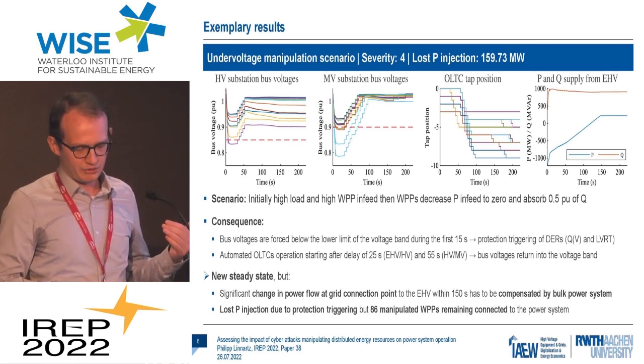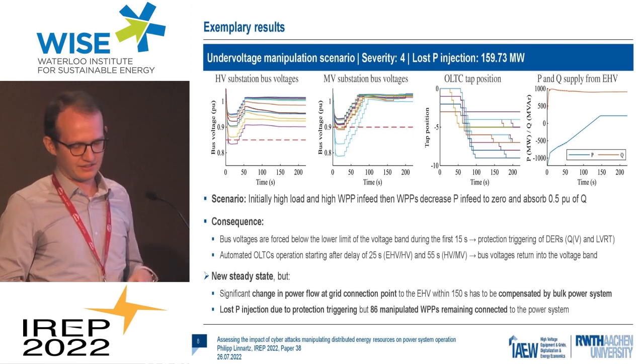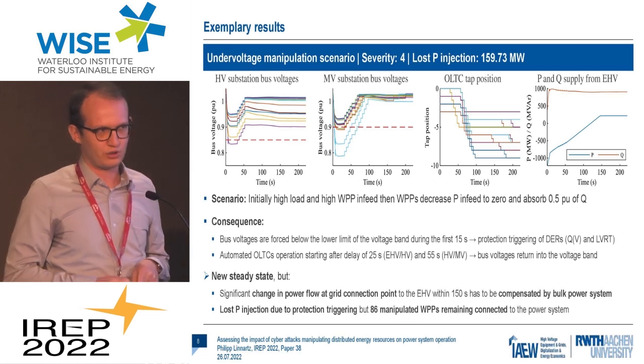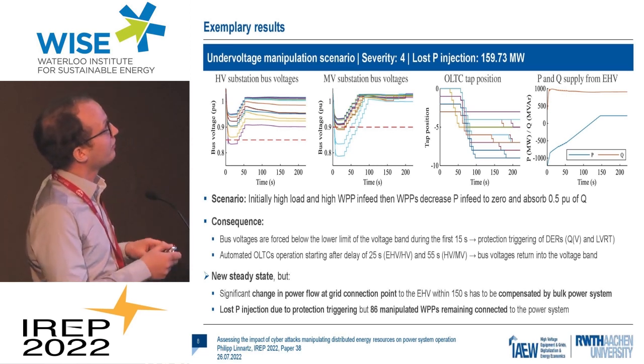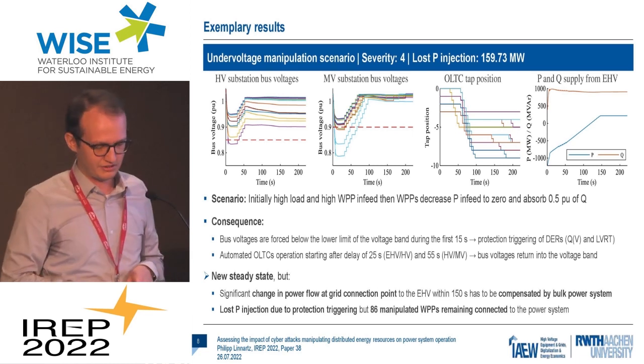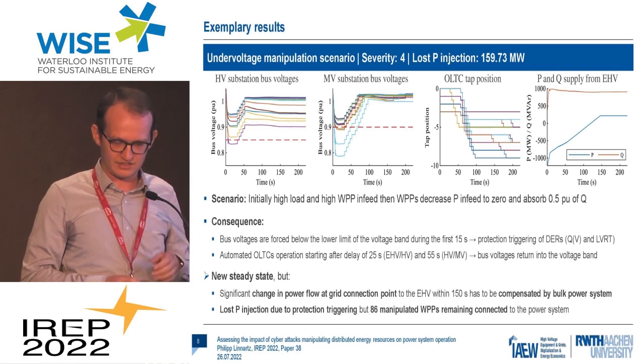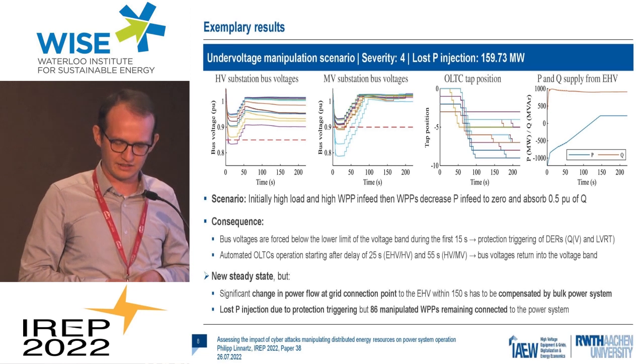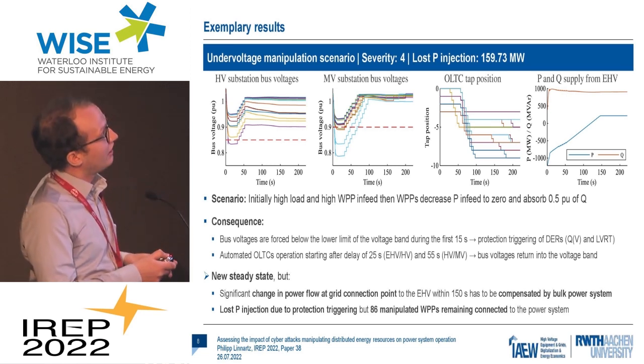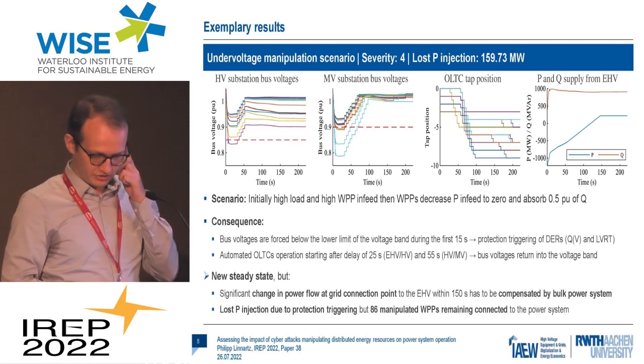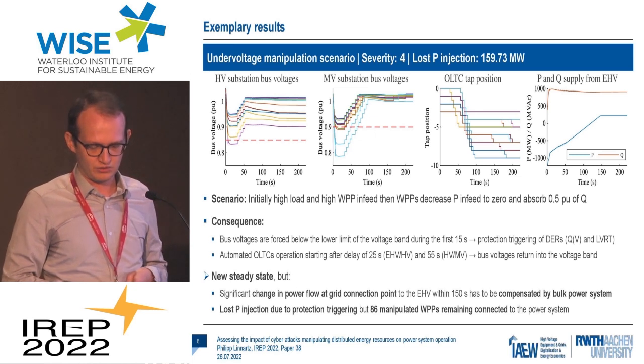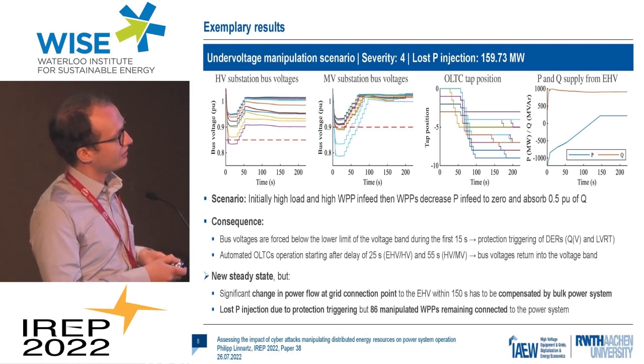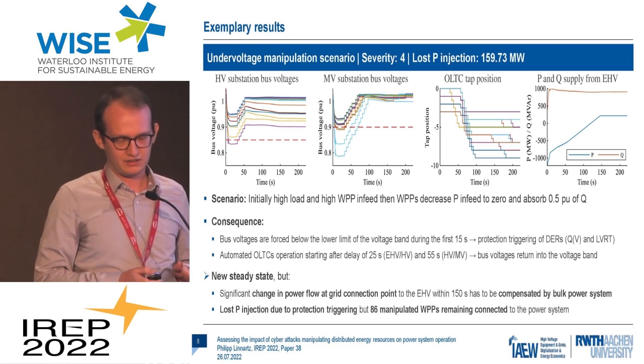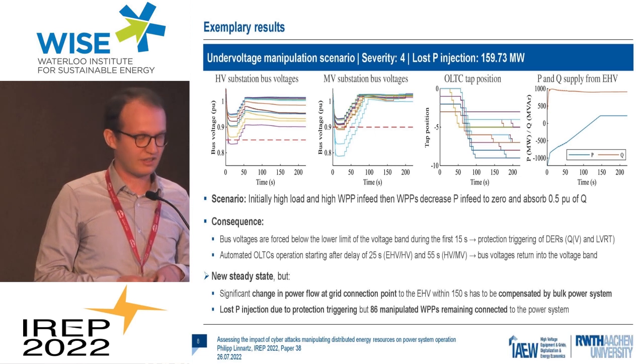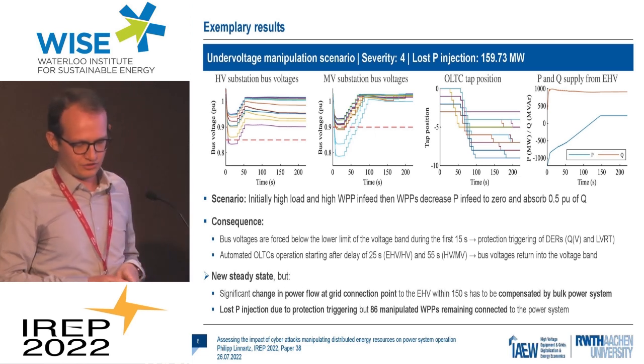The scenario was initially high load and high generation in feed, and then the attacker sent the commands to decrease the active power in feed to 0 and to absorb 0.5 per unit of reactive power. What happens immediately in the first 10-15 seconds is that the bus voltages decrease very fast. That's due to the time constant of this reactive power application, which is much faster than the active power anyway. After 10-15 seconds, the first DERs trip due to the bus voltages being too low, even inside these low voltage ride-through requirements. So we end up in this new steady state for some 10 seconds. If we stayed there, after 60 seconds or so, even more devices would disconnect due to undervoltage protection.